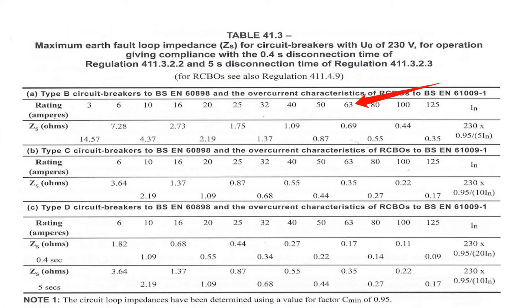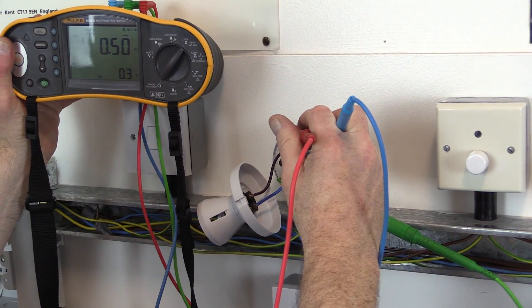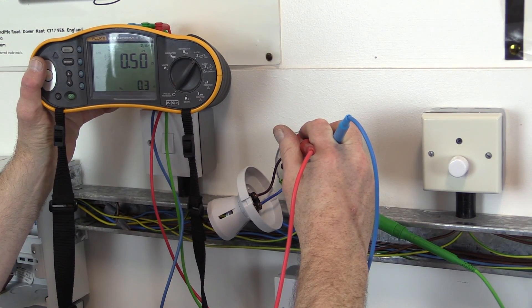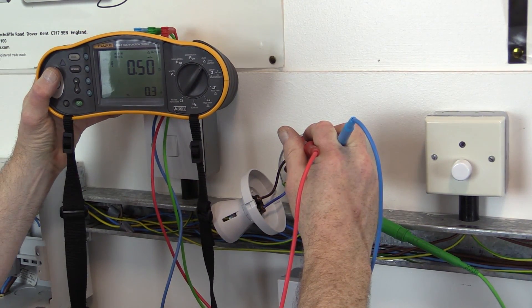It would also be recorded on the top left-hand side of the schedule of test results which will be produced for the single-phase distribution board. In this example, we measured a value of 0.50 ohms. For a 63 amp BSEN 60898 type B circuit breaker, this is given in Table 41.3 at 0.69 ohms, but would have to be adjusted by a factor of 0.8 to allow for the theoretical increase in temperature. Referring to the temperature-adjusted values in the IET on-site guide, Appendix B Table B6, this table identifies the maximum value as 0.56 ohms. As the measured value of 0.50 ohms is less than this, it is satisfactory. We can then proceed to carry out the earth fault loop impedance tests for each circuit connected to the three-phase distribution board and for those connected to the single-phase distribution board using one of the options outlined.